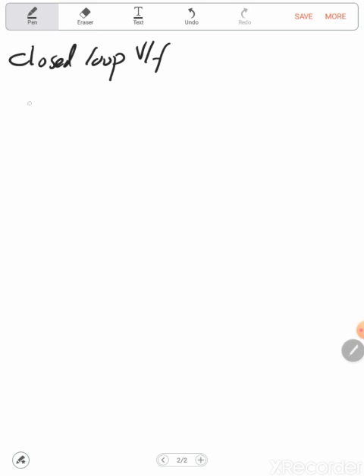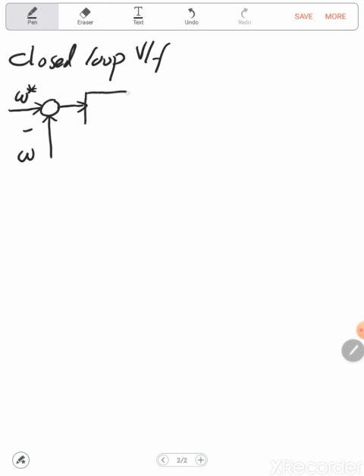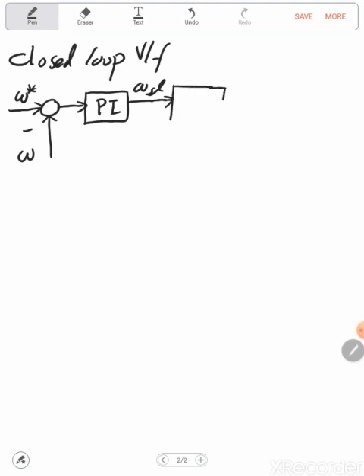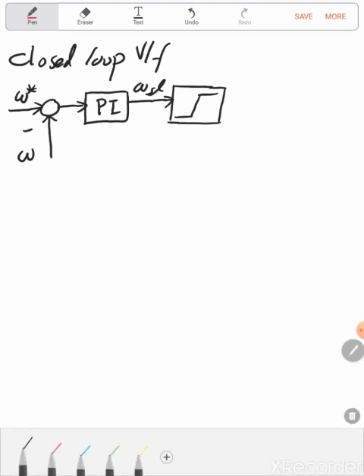Let's assume that we have omega reference. In closed loop we need to measure the output and compare it with the reference, so let's assume we have the actual output omega_r. This will be the error signal. In general we need to minimize the error signal, and for that we'll use PI control. The output of the speed controller is proportional to the torque, and the torque is proportional to omega slip. In order to avoid instability we can add a slip limiter.